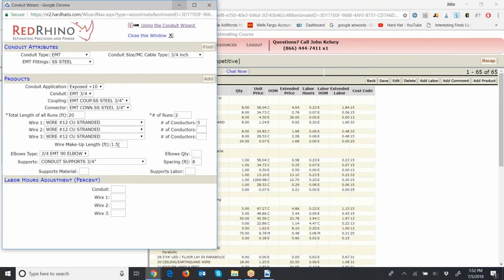Okay, now what I want to explain here is wire makeup length. The amount of wire, this program inputs the number of feet of wire makeup that you put there. The wire makeup length is defined as the amount of wire sticking out beyond the end of the conduit to go to the termination point. Look, if you're coming out of the top of a panel, sometimes it might have to go 3 feet down to terminate to the circuit breakers. In this case, it's set for 1.5 feet. I'm going to make it 3 foot. So I just set that.